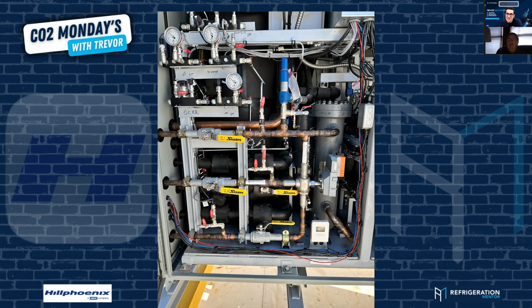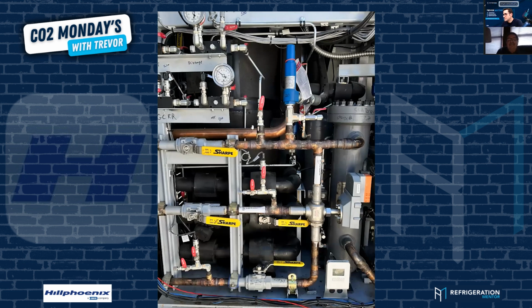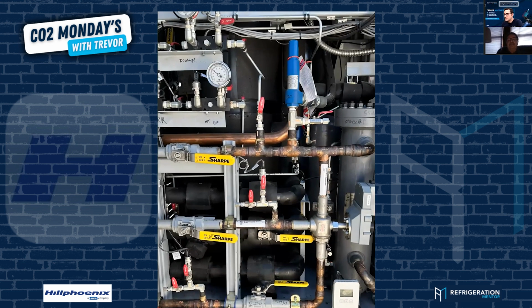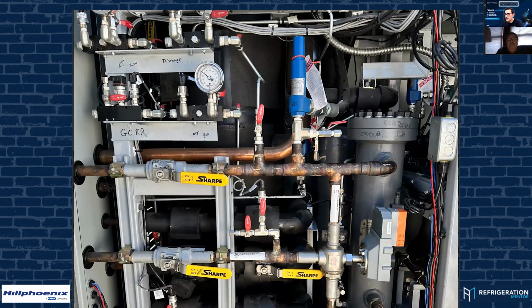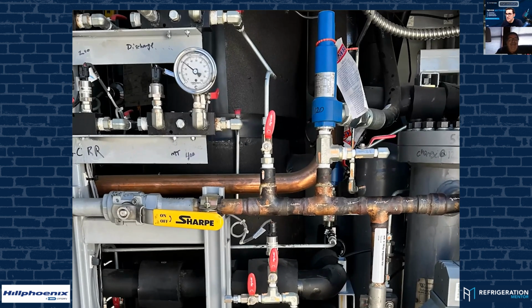You guys designed a system for what the customer's asking, but that is tight. Like that accumulator right back there. Yeah, that's the receiver, reservoir from the opposite side. But boy, if you look in there, you can hardly see, but straight back at the top of that separator to the left is the gas bypass valve, just on the other side of that pipe clamp. Yeah, you'll never see it. Trust me, there's one right there. There's the flash gas bypass valve way back there.